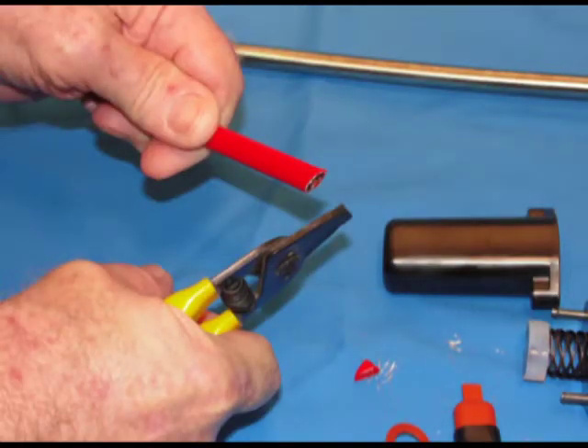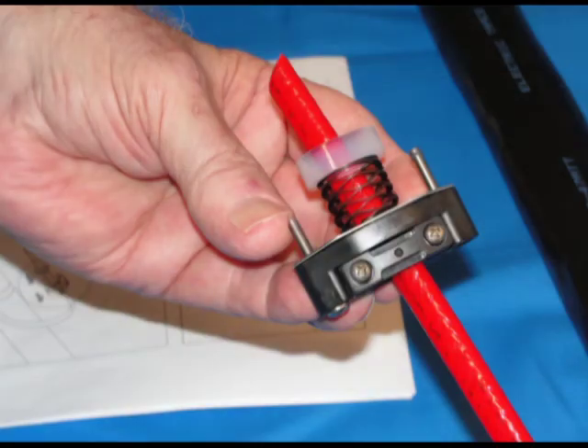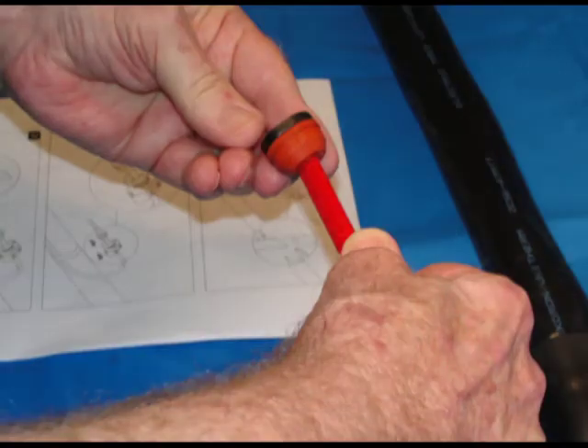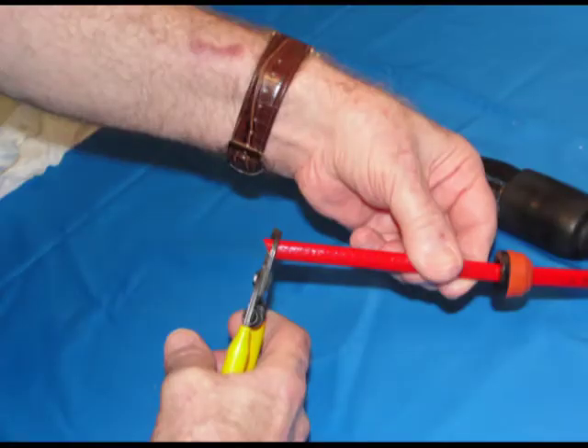Allow approximately 12 inches of heat tracing for proper termination. To aid in installation, cut the end of the heat tracing to a 45 degree angle. Slide on the lower portion of the enclosure housing. Next, slide the sealing grommet onto the heat tracing as shown. Trim heat tracing to a 90 degree square end.